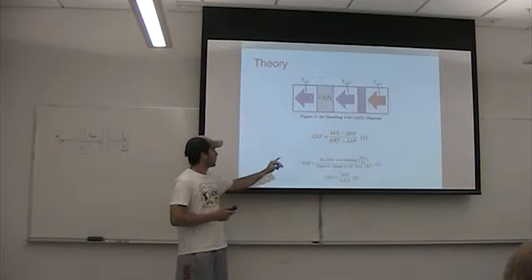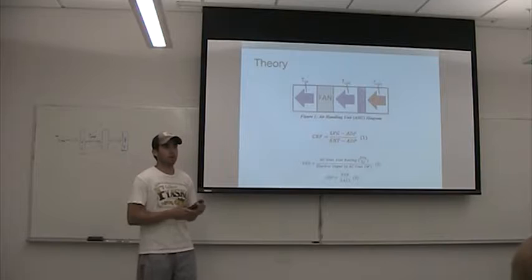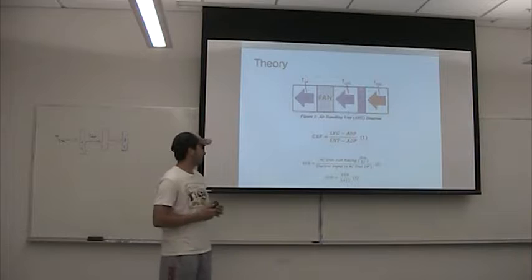So right here, this is the coil bypass factor. It should be between zero and one. The closer it is to zero, the more efficient these coils are at cooling the air. So we're going to have to find that.